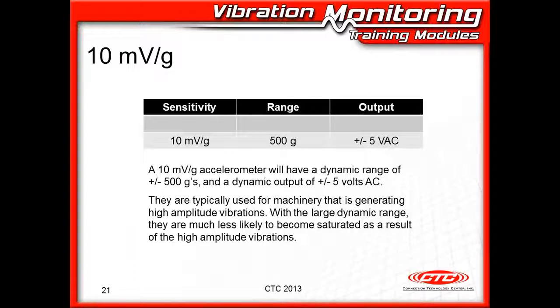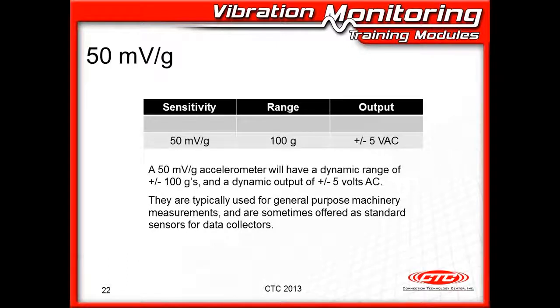If we have a 10 millivolt per G accelerometer, this is an accelerometer that's going to be used for something that's vibrating badly. There's going to be a lot of vibration. It's going to be very harsh. You might find this on a shaker screen. You might find this on a reciprocating pump because there's a lot of impacting on that recip. And the benefit here is that you have 500 Gs of dynamic range. So 10 millivolts per G times 500 Gs will give you a plus and minus 5 volt AC output at its maximum.